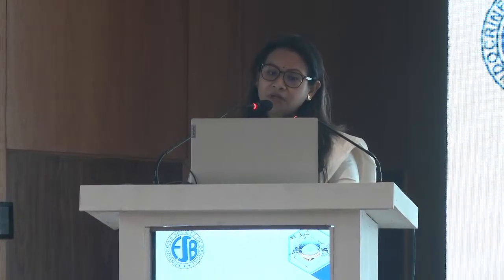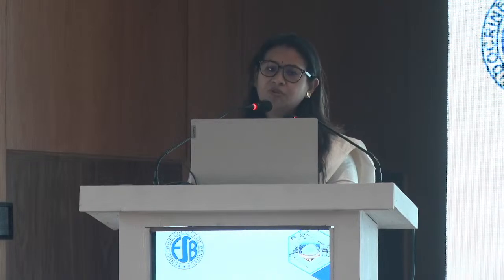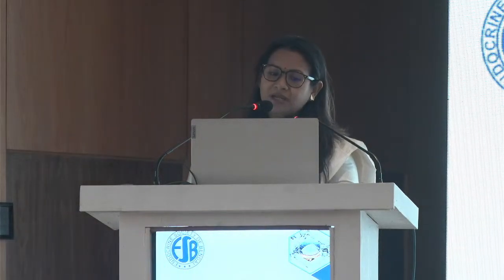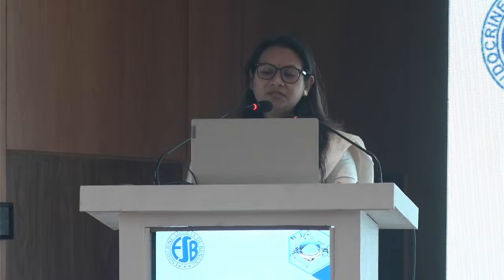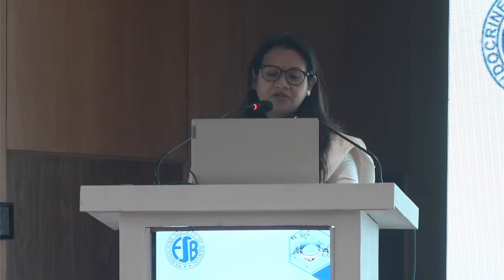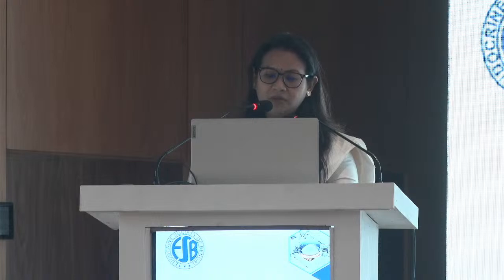But the admonition in pediatric densitometry, we should all remember that children are not simply small adults. Children are definitely different from adults because the pediatric skeleton is constantly changing in size as well as shape. Ossification centers fuse at different age groups. Chronological age may not reflect the bone age. Onset of puberty has a pronounced effect on the skeleton. Again, we have to think about radiation safety, reference database, and usually we use Z-score rather than T-score in pediatric BMD. Again, the software must also be able to detect low density bone edges.